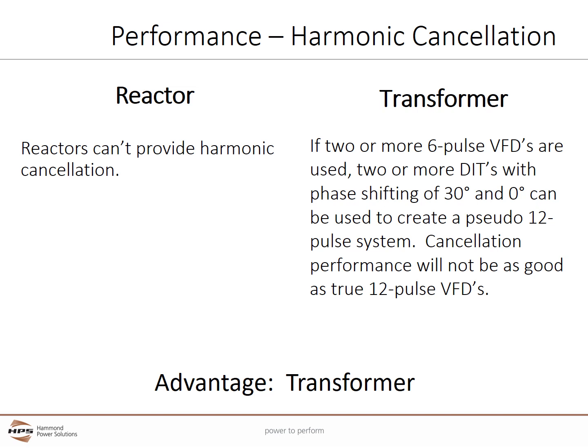However, if you have two standard 6-pulse VFDs of equal size or can group two sets of multiple VFDs into roughly equal loads, you can do a neat trick with DITs. You can order one set of DITs as standard delta-Y with a normal 30 degrees phase shift, and a second set with a zigzag secondary that can give 0 degrees phase shift. This creates a kind of 12-pulse system that creates actual harmonic current cancellation at the larger transformer feeding these two phase-shifted transformers. A couple of caveats with a system like this.